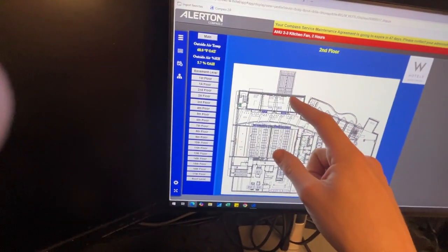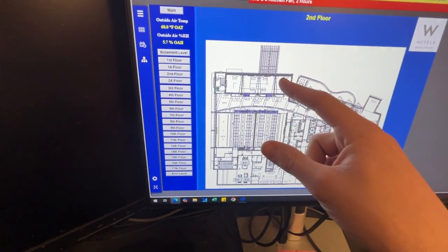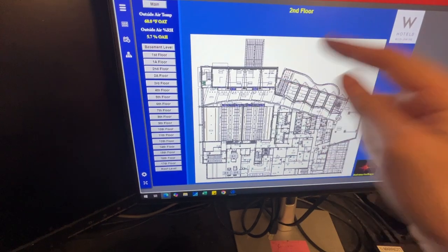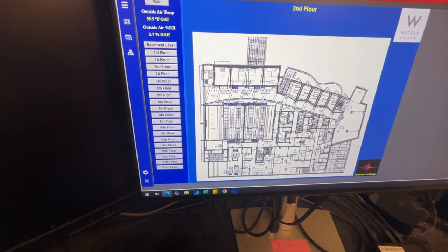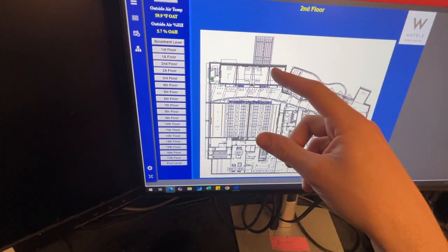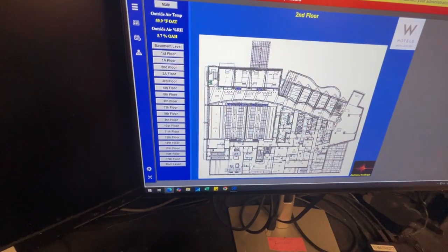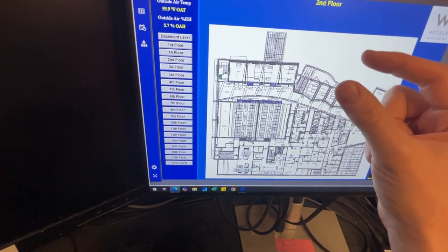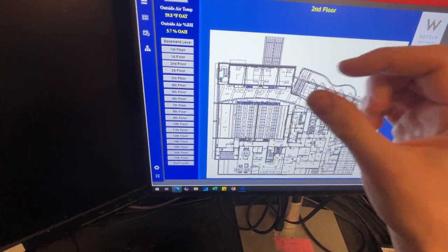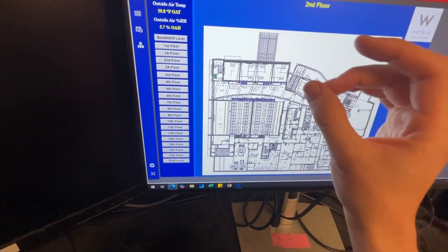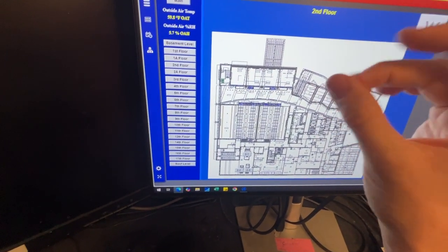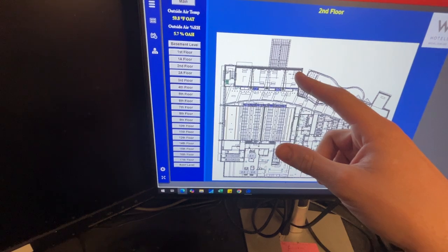The valves themselves are only rated for like 160 PSI, but the pumps are on the roof and the pressure from it coming down from the roof is like 170. So the pressure in the pipe is over the rating of it. So the valves, I think, are not able to fully close. And the spring inside, when it gets cold enough, there's a thermostat inside that valve, and it goes ba-bum, ba-bum, ba-bum, ba-bum, because it's trying to stop the pressure from happening.